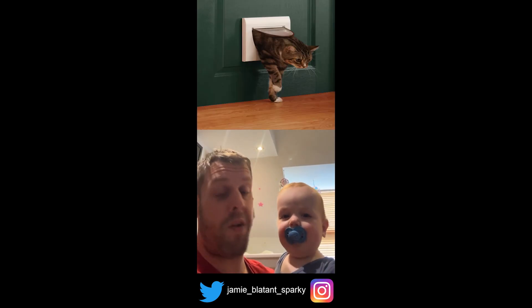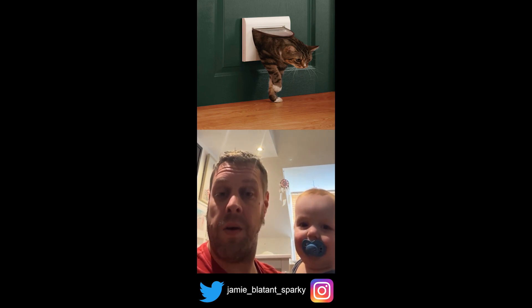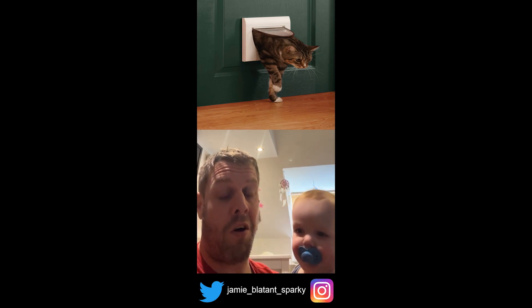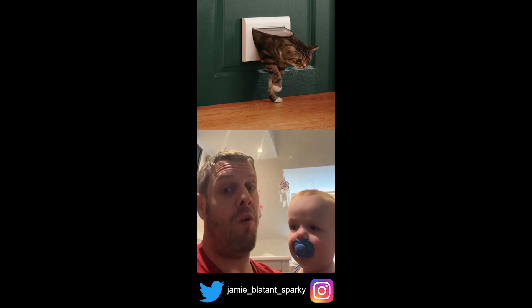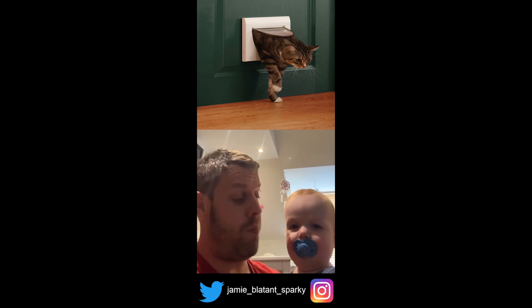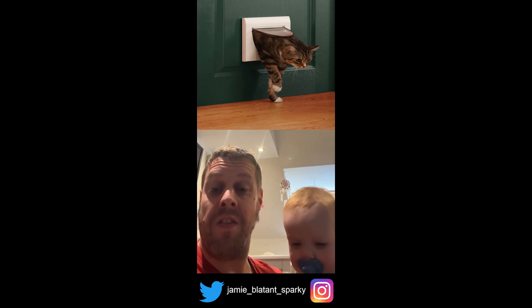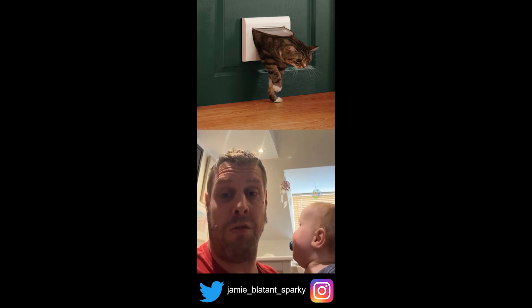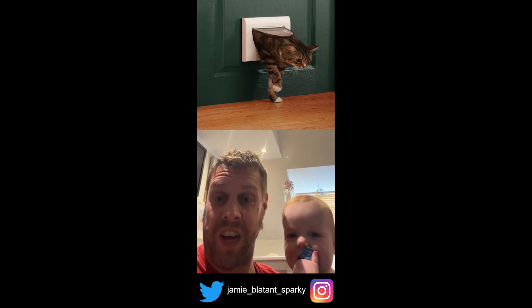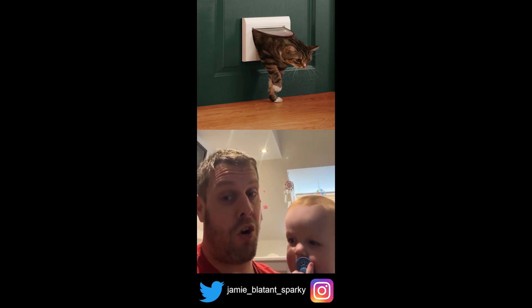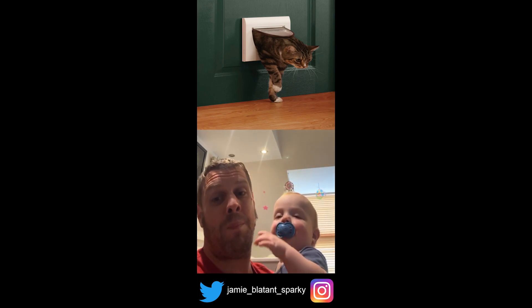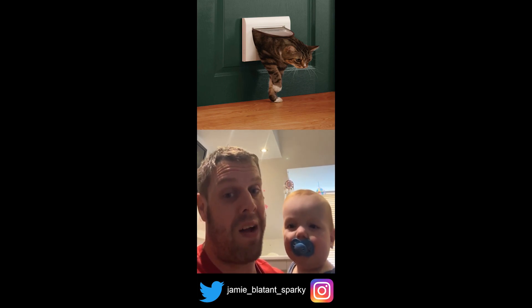At some point between opening and closing, the cat flap won't meet any sensor, so it'll come up as faulty. Then you start getting all these layers of code — you know if it's closed because the sensor's on, you know if it's open because the sensor's on, but if neither sensor has been activated it could just be moving between positions. Then you have to start incorporating things like snub timers to ignore the fact it could appear faulty for a few seconds. That's when PLC coding gets hard — you've got to think really logically about everything.